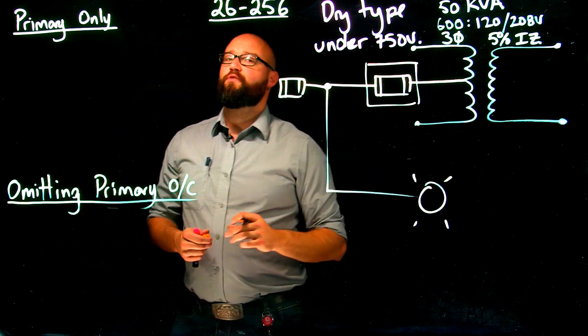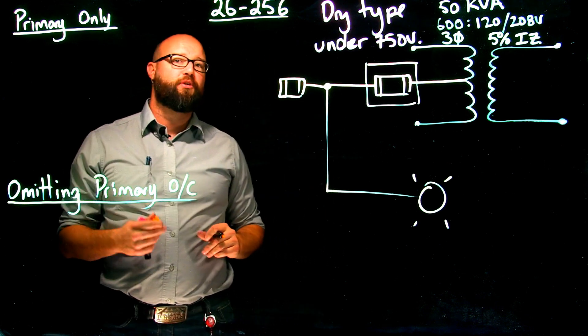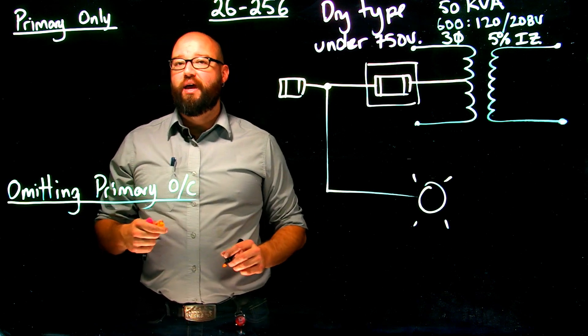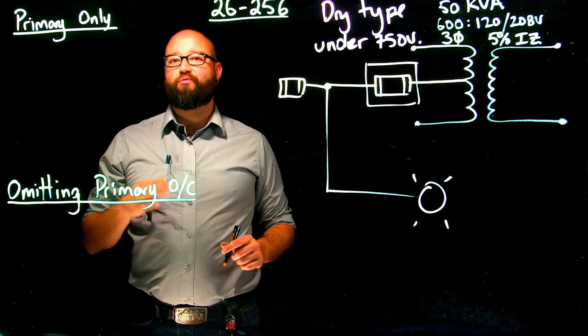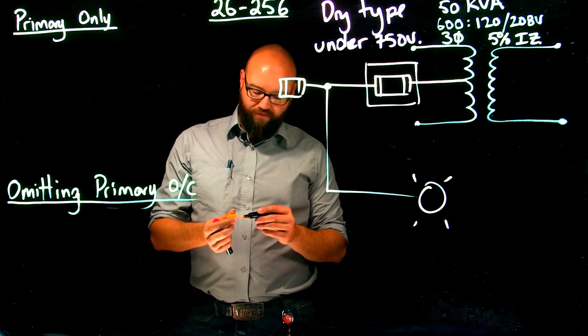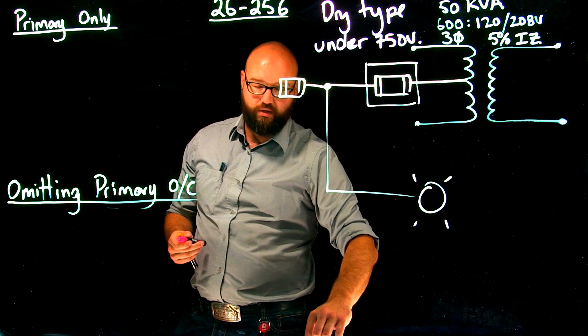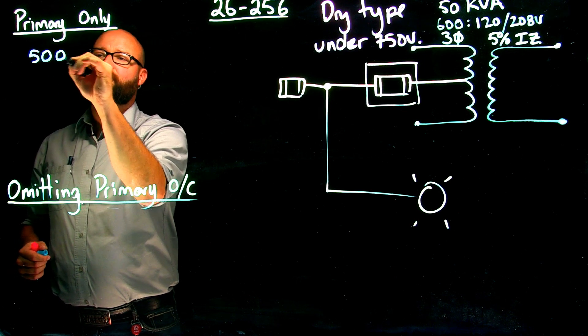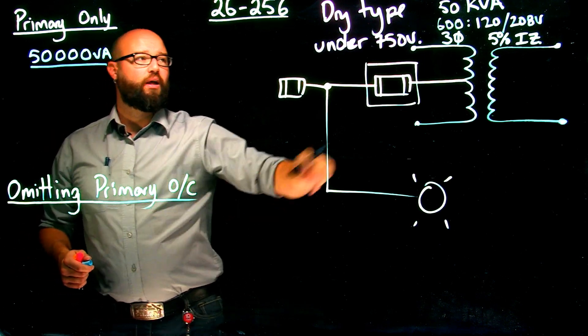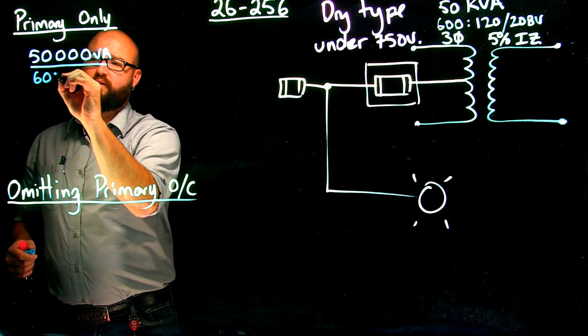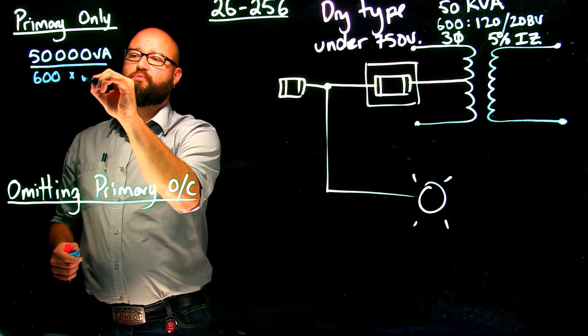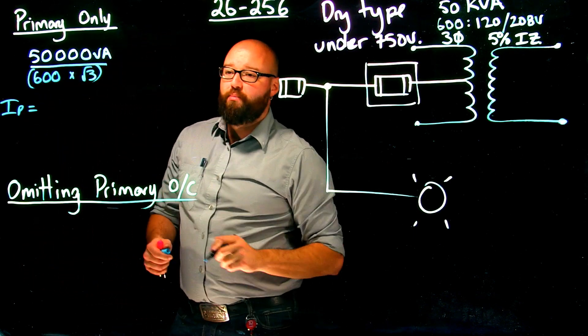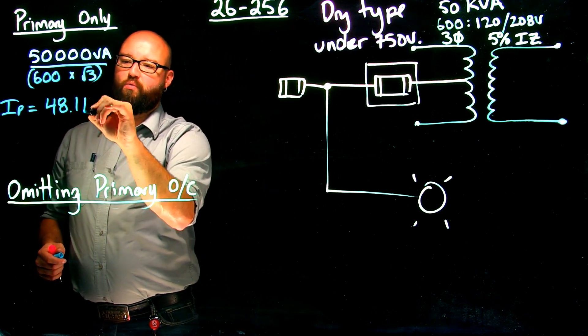This is just for individually sizing our overcurrent to our individual primary. So if we take a look, 26-256 subrule one tells us that if I have primary protection on a dry type under 750 volt transformer, it shall be set at not more than 125% of rated primary current. So first of all, obviously we need to figure out what is our rated primary current. We are going to take a look. We have our 50,000 VA or 50 kVA divided by my line voltage of 600 volts. And again, because it is a three-phase transformer, we're going to go times root three. We end up with an I primary or rated primary current of 48.1 amps.